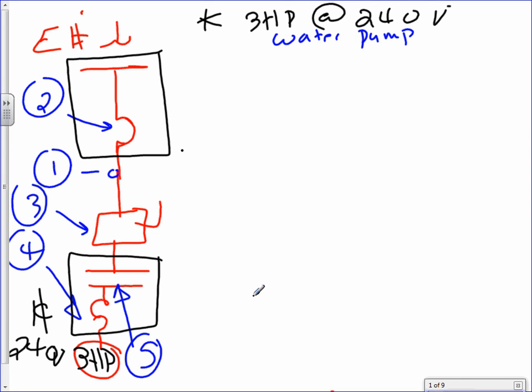So the branch circuit. The third one is the disconnect. The main reason for having the disconnect is because we want to continue to have 10 fingers, 5 fingers in each hand, and we don't want to get electrocuted, right? Safety. Okay, number 5. Why do we have number 5? The controller. Why do we have a controller for a sump pump? Do you really want to go to a water pump and turn it on and off every time you need water, or do you want it to work automatically? You want it to work automatically, so we have a controller. So number 5 is a controller.